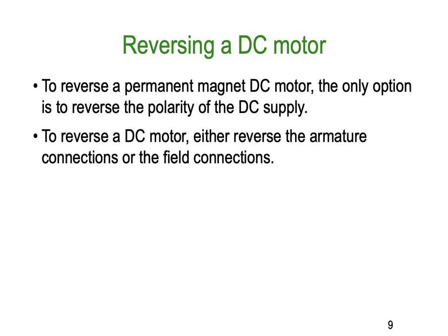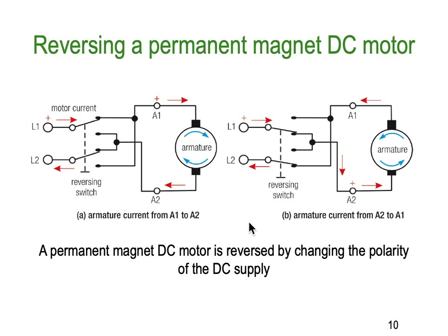To reverse a DC motor you've either got to reverse the armature connections or the field connections. If you reverse both, both change in the same direction and your motor won't reverse. Reversing a permanent magnet motor is typically done with a two-pole changeover set of contacts. Here's our supply plus and minus, with two sets of contacts mechanically operated together as a reversing switch with changeover contacts.